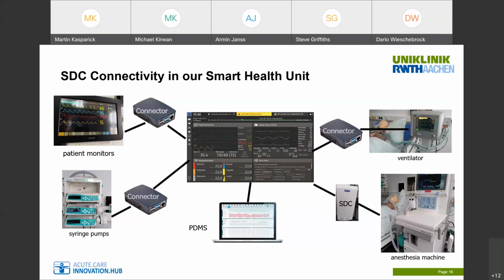To a certain extent. I guess I'm asking, each device is going to have an MDIB for the SDC communication. And I assume there's going to be some kind of one-to-one correspondence between the data or control commands that are available and can be given on the proprietary side, and the BICEPS model or the SDC model that the network is translating.